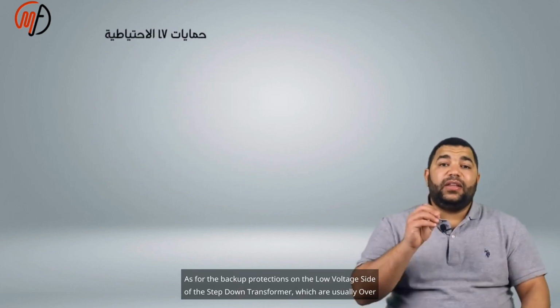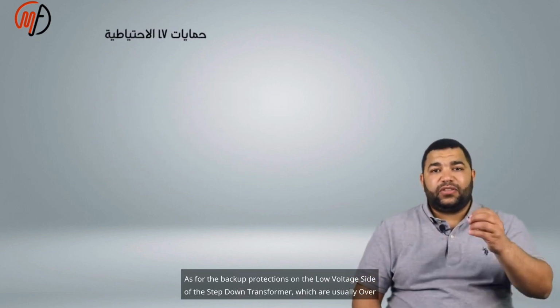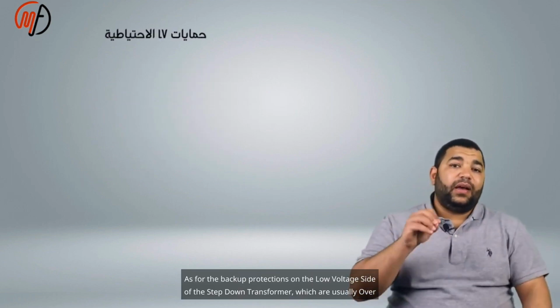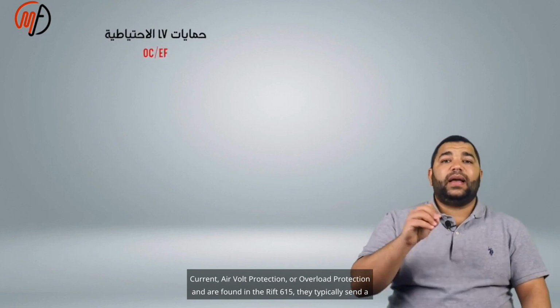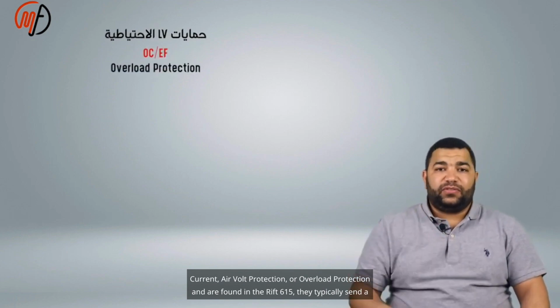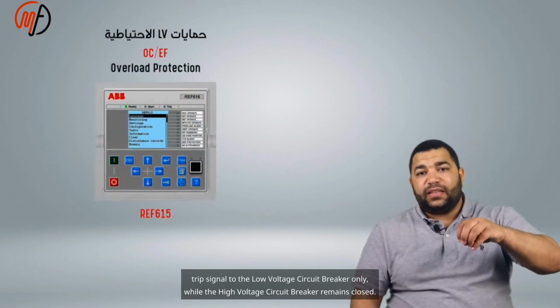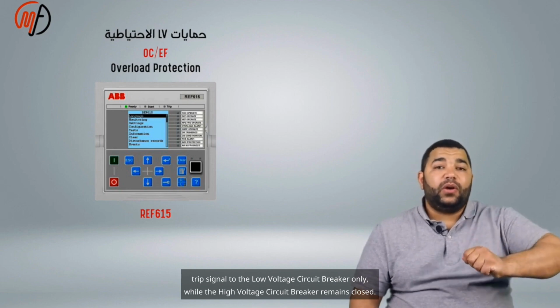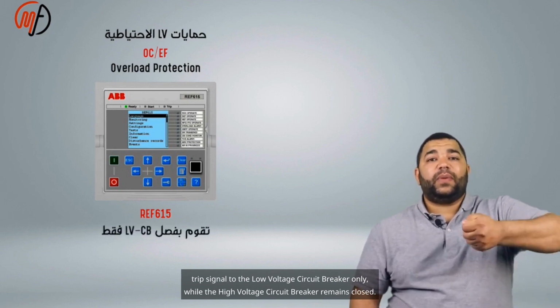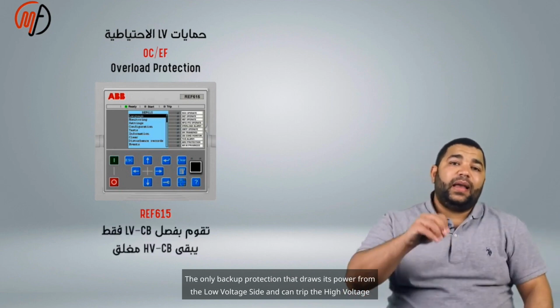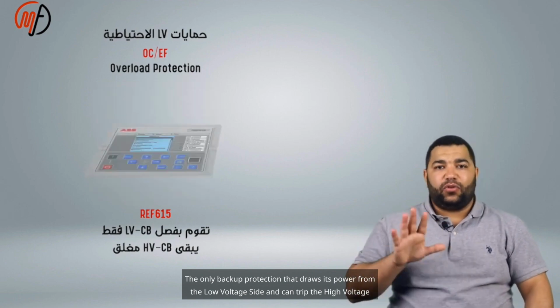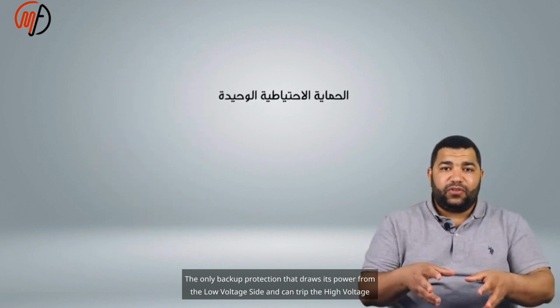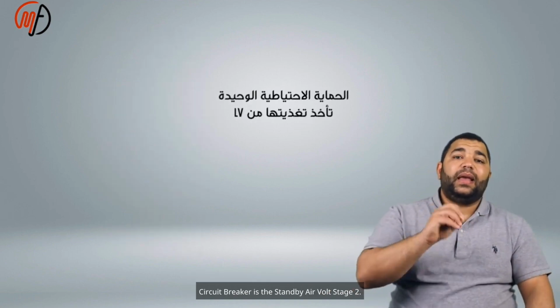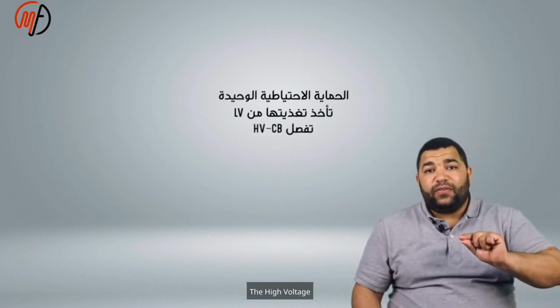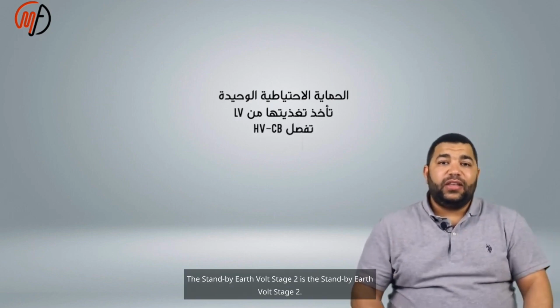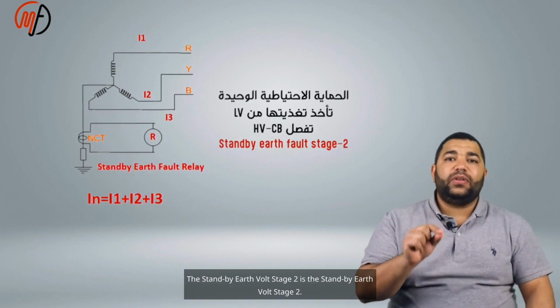As for the backup protections on the low voltage side of the step-down transformer, which are usually overcurrent protection or overload protection and are found in the REF615, they typically send a trip signal to the low voltage circuit breaker only, while the high voltage circuit breaker remains closed. The only backup protection that draws its power from the low voltage side and can trip the high voltage circuit breaker is the standby earth fault stage 2.